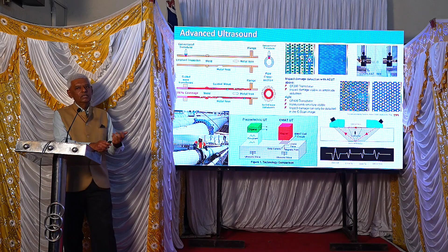We realized, for example, in a heat exchanger, when we have a support plate or baffle plate, if there was a defect under it, we were unable to detect it with a single frequency, and then came multi-frequency. We realized we could do a very good job if the material was electrically conductive, like copper, brass, stainless steel. But what about carbon steel?